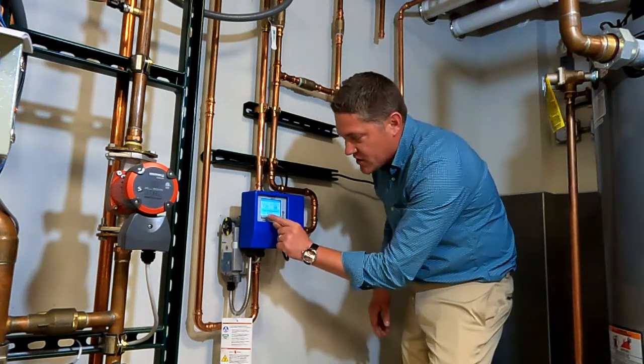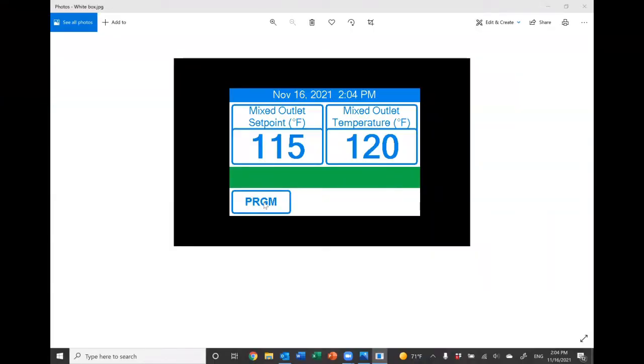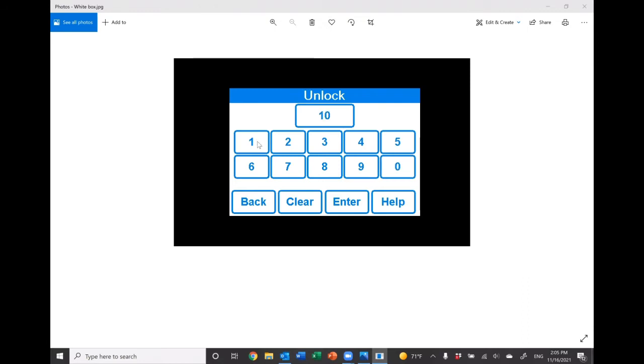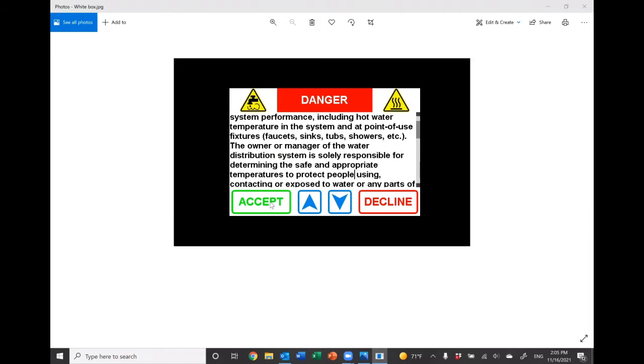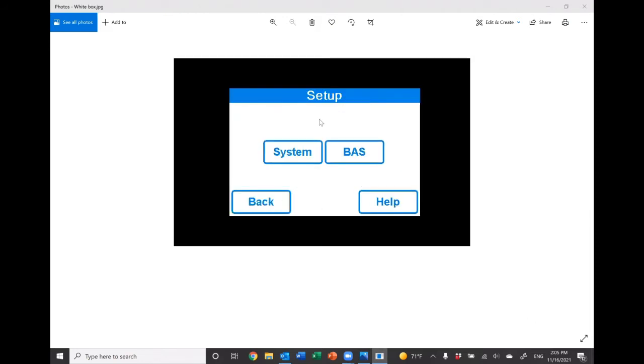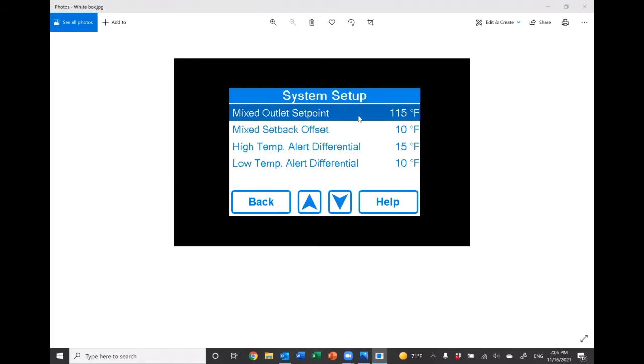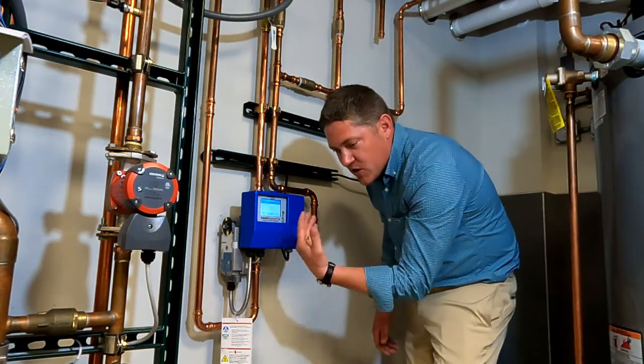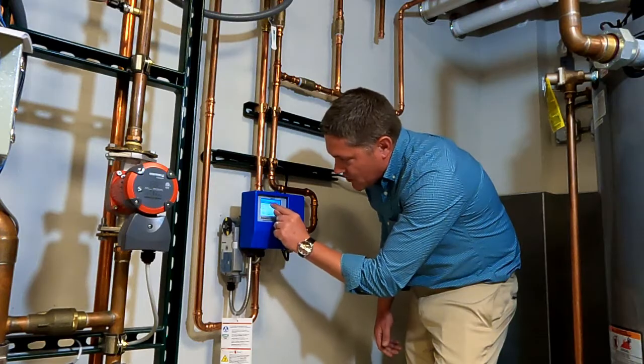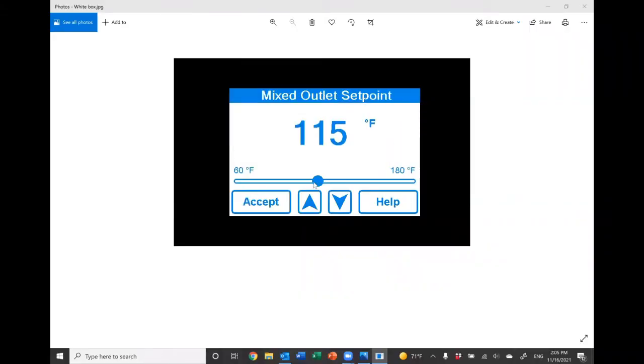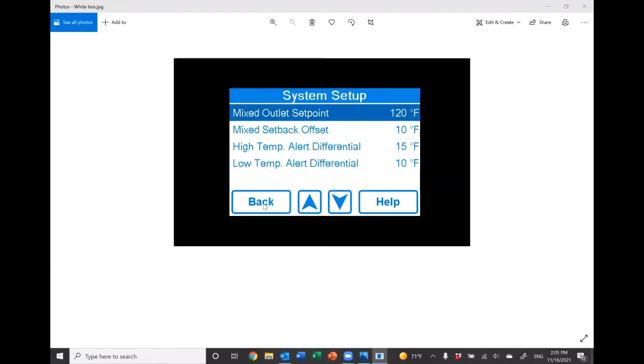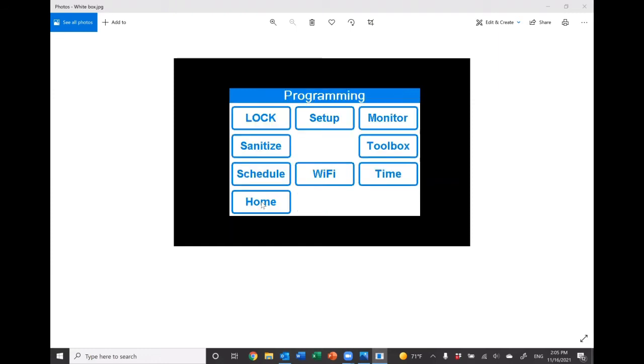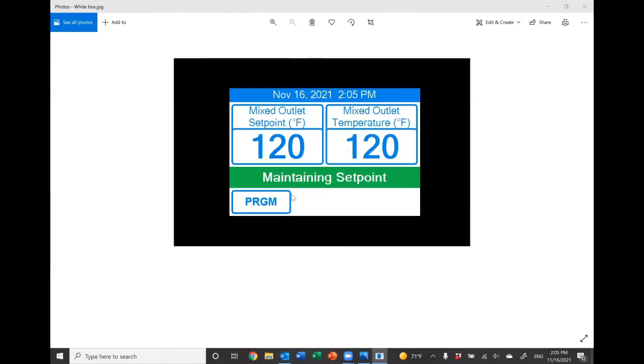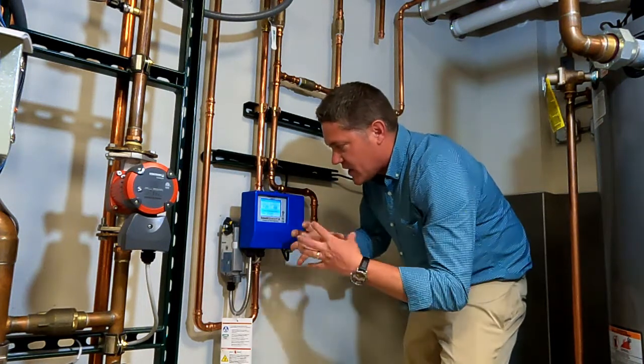As far as setting it up, it's very similar to the Intellistation Sr. Program, unlock, and then we put in a factory default code, or the one that the facility has set up. Hit enter, accept the terms, go to settings, or setup, system, and then you have 4 options there. Valve selection: is it a 3/4 or a 1 inch, or the larger diameter is 1.5 inch or 2 inch. And then you've got your mixed set point. On your mixed set point, you've got the touch screen sliding scale to where I can adjust the temperature to whatever I want, or use the arrows to change it 1 degree at a time. Once I've got it dialed in to 120, what I want it set at, I hit accept. I can go back, go to the home screen, and it's going to show me what my mixed temperature is and what my set point is.